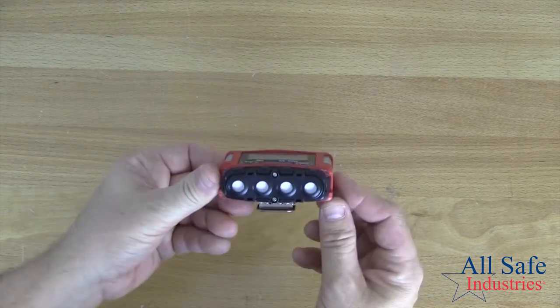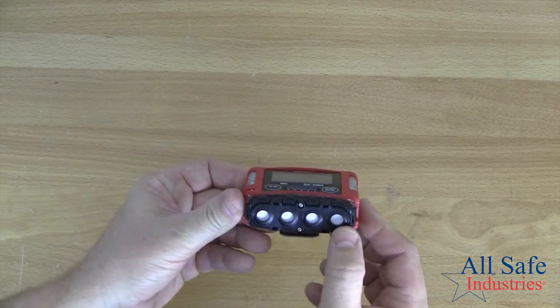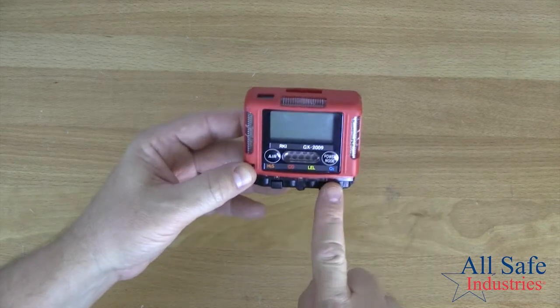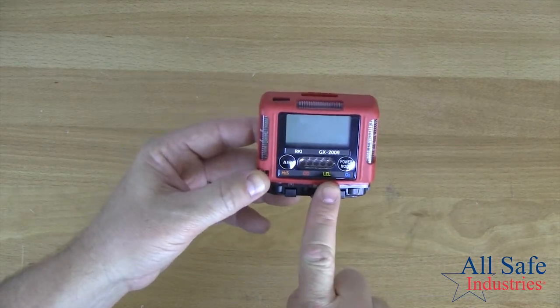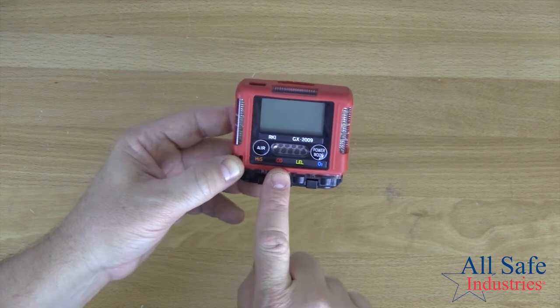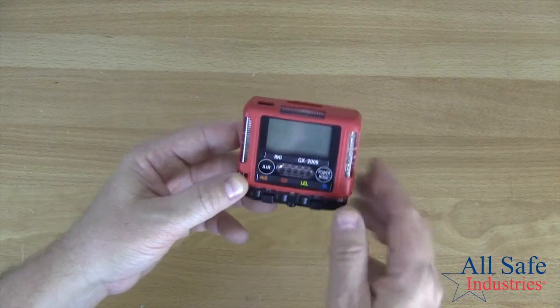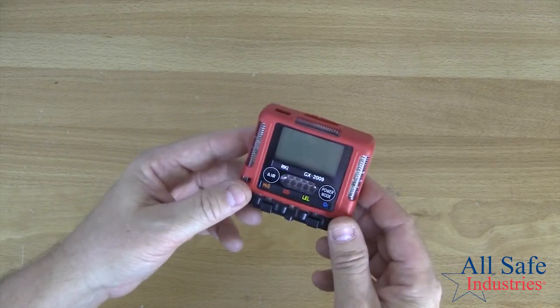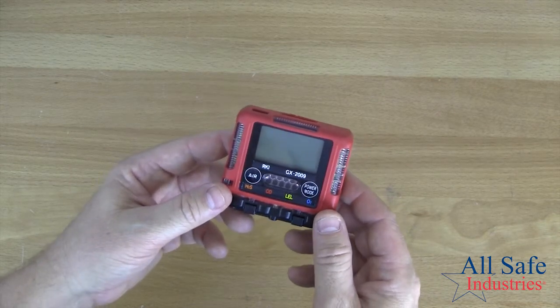So this instrument does monitor 4 different gases with 4 separate sensors. It monitors oxygen, LEL, which is your flammable gas sensor, carbon monoxide, and hydrogen sulfide. So these are the 4 gases that we monitor for in industry most frequently.